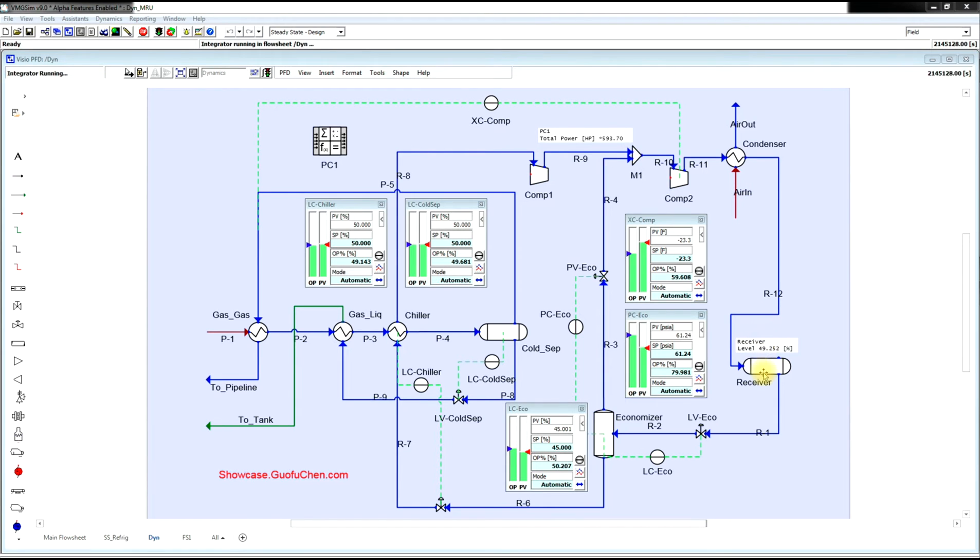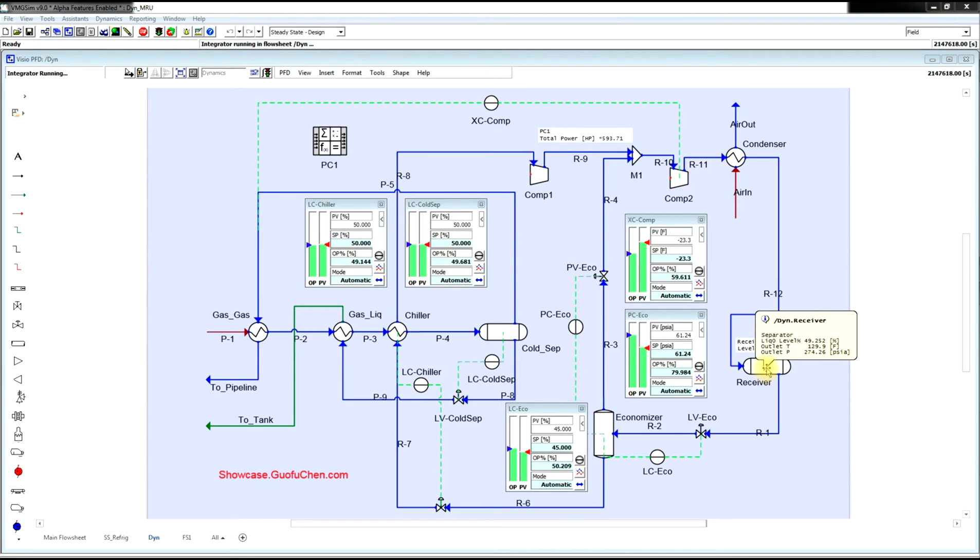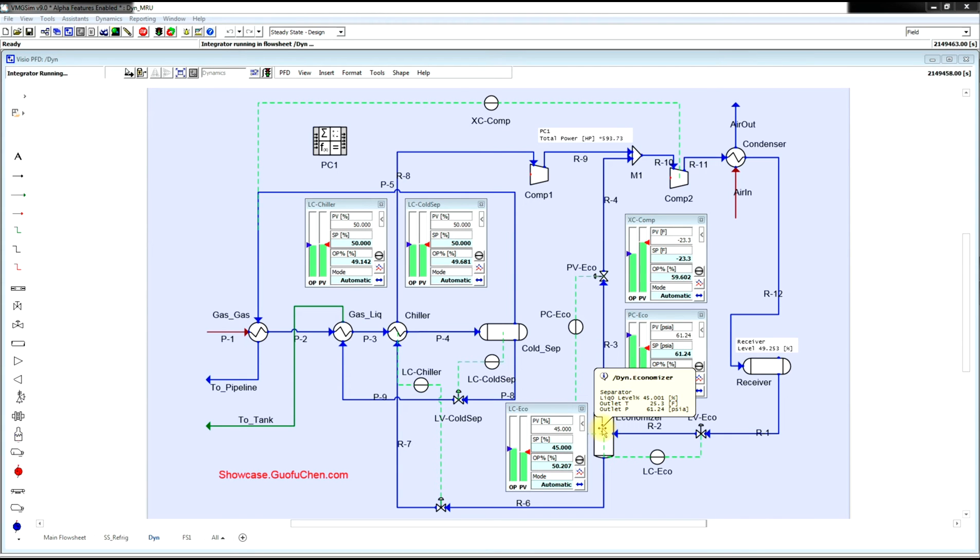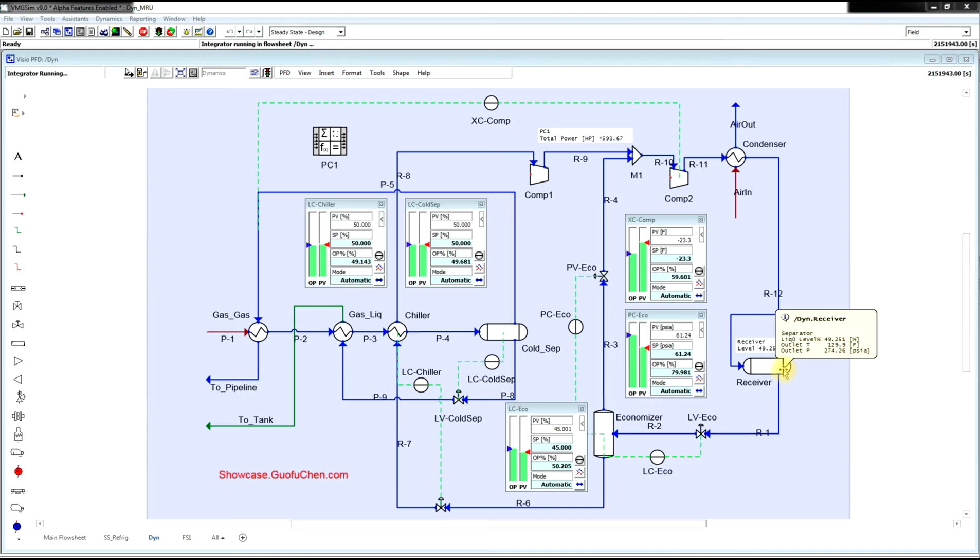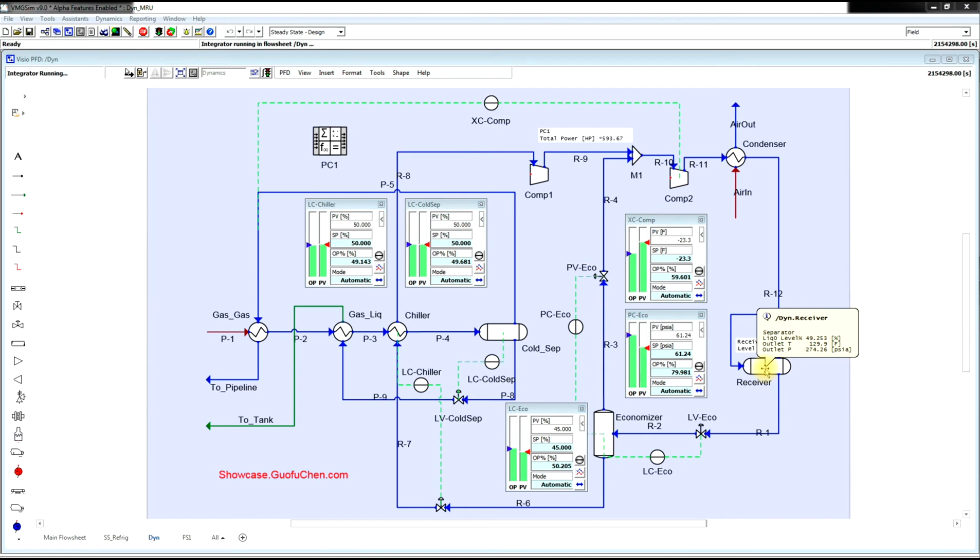Since we have a receiver, do you think we need to have a liquid level controller on the receiver? No, we actually control the liquid level in the economizer and in the chiller. Since the total mass in the refrigerant loop remains the same, the liquid level in the receiver is going to be whatever it is.